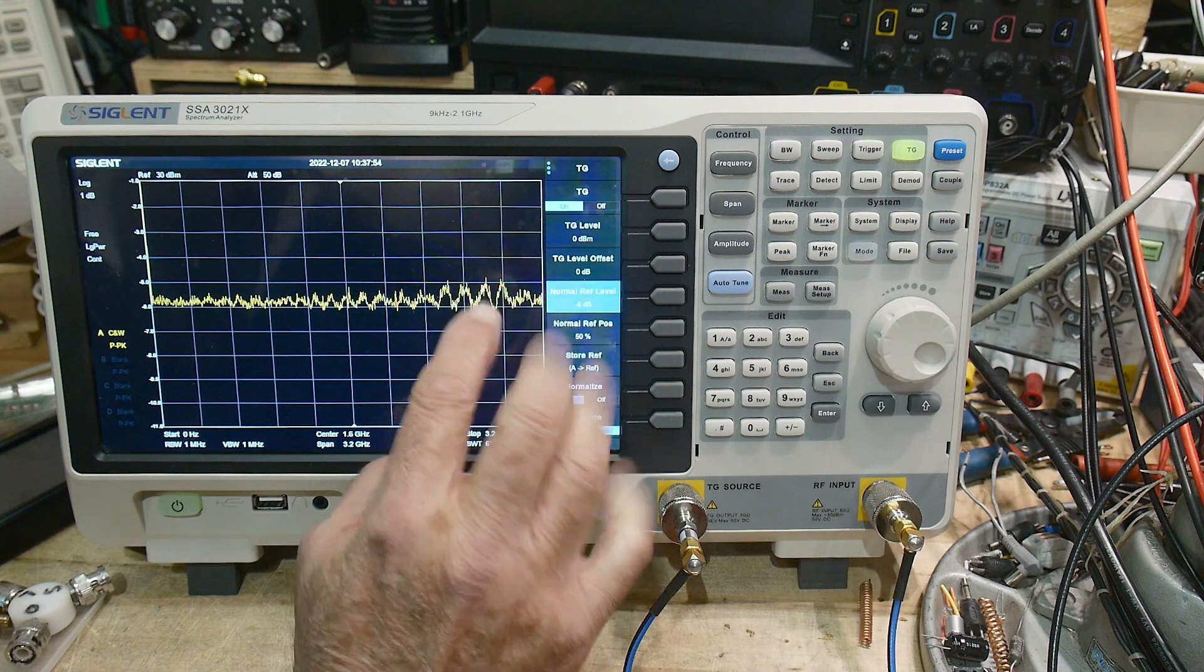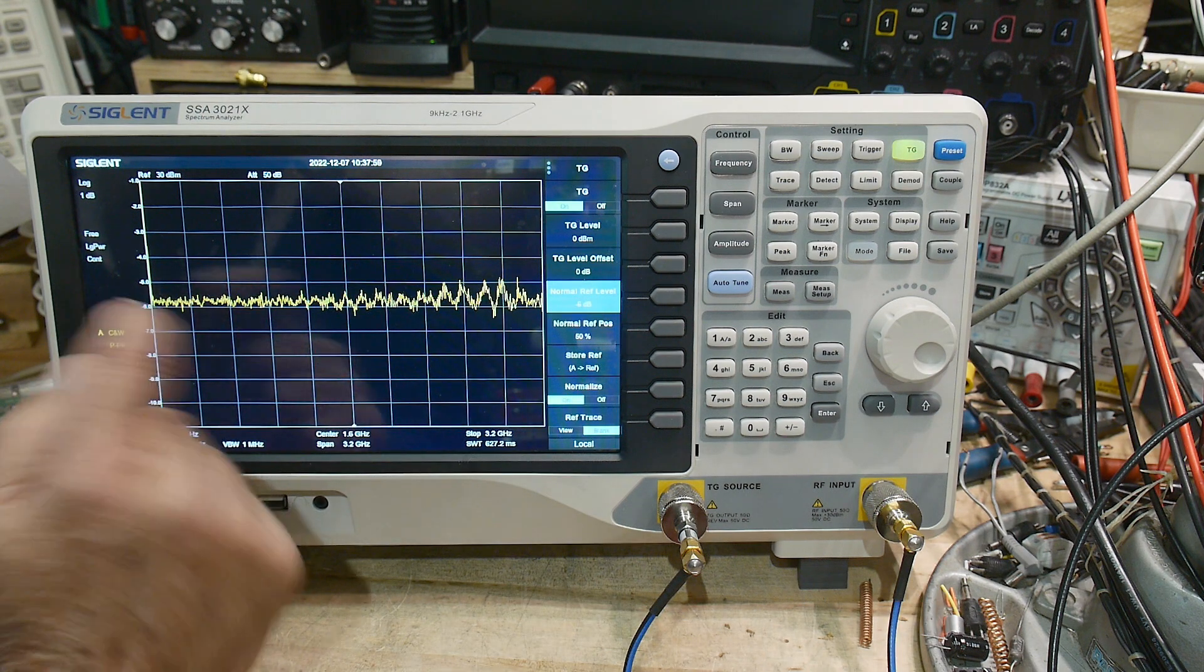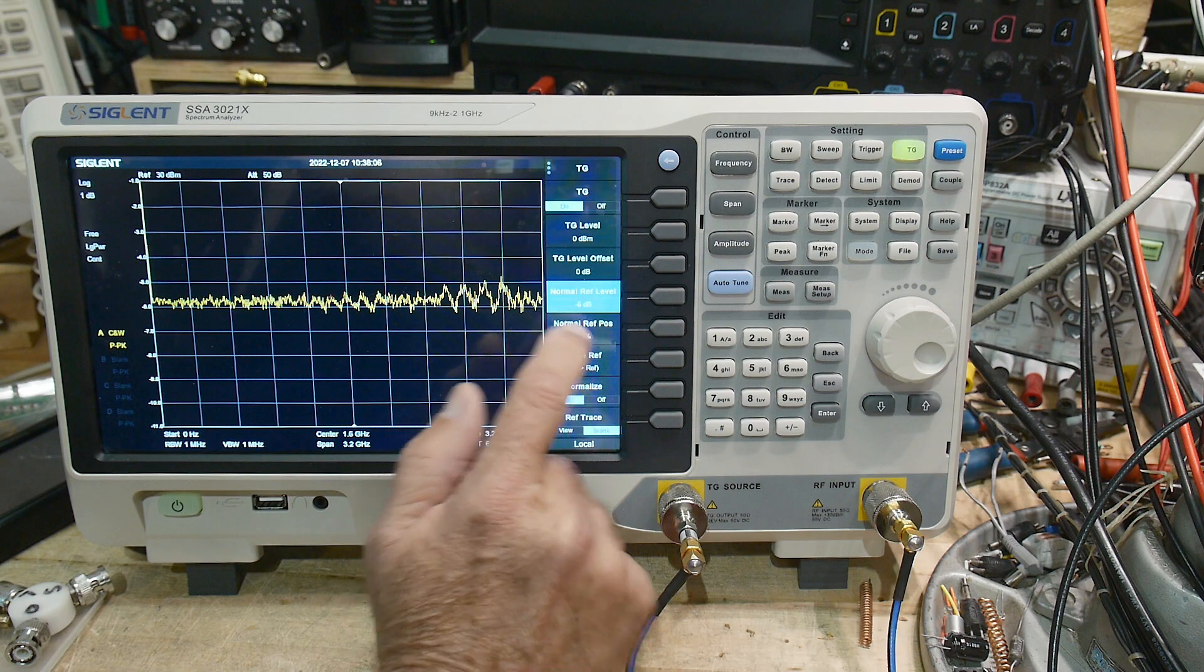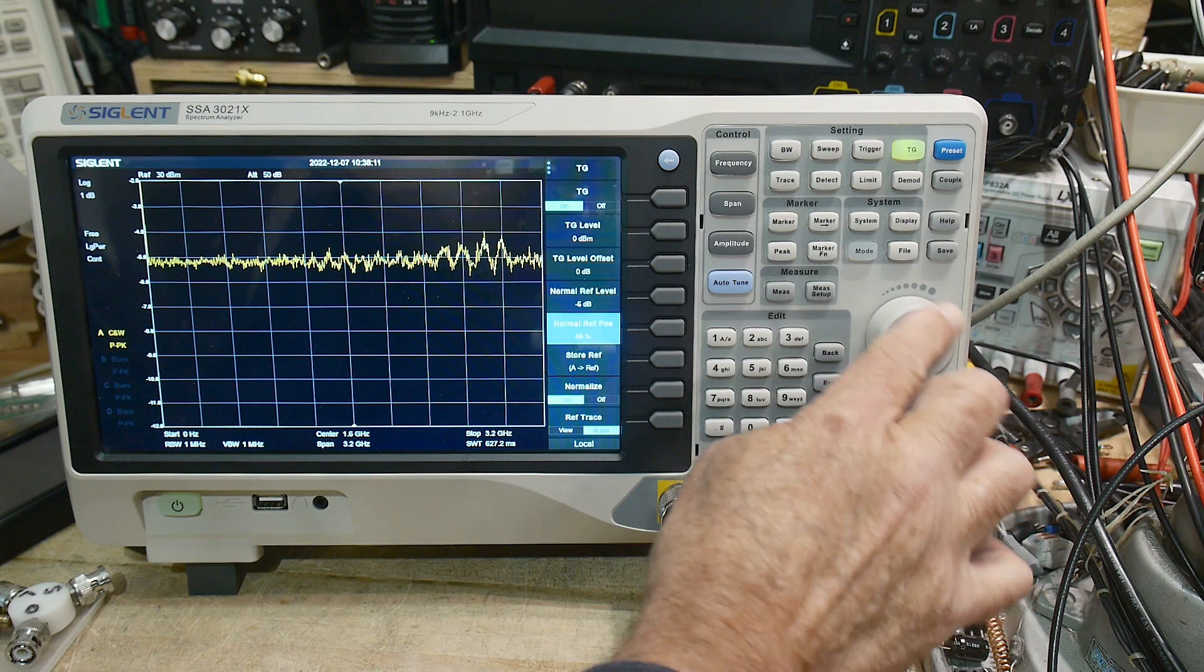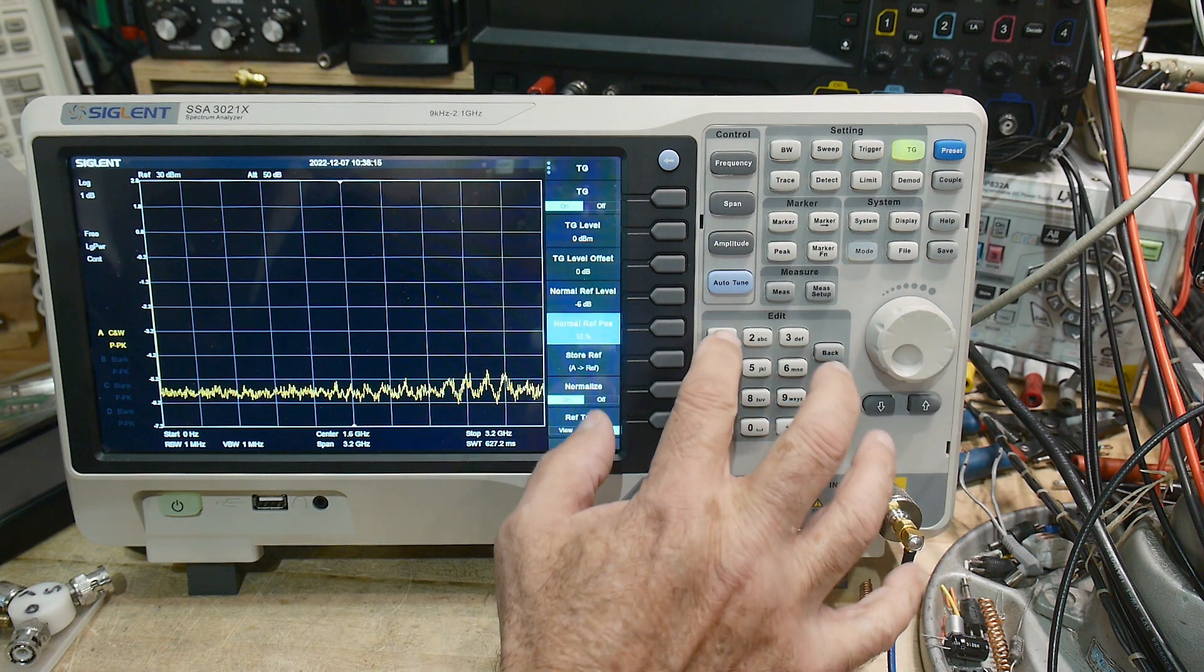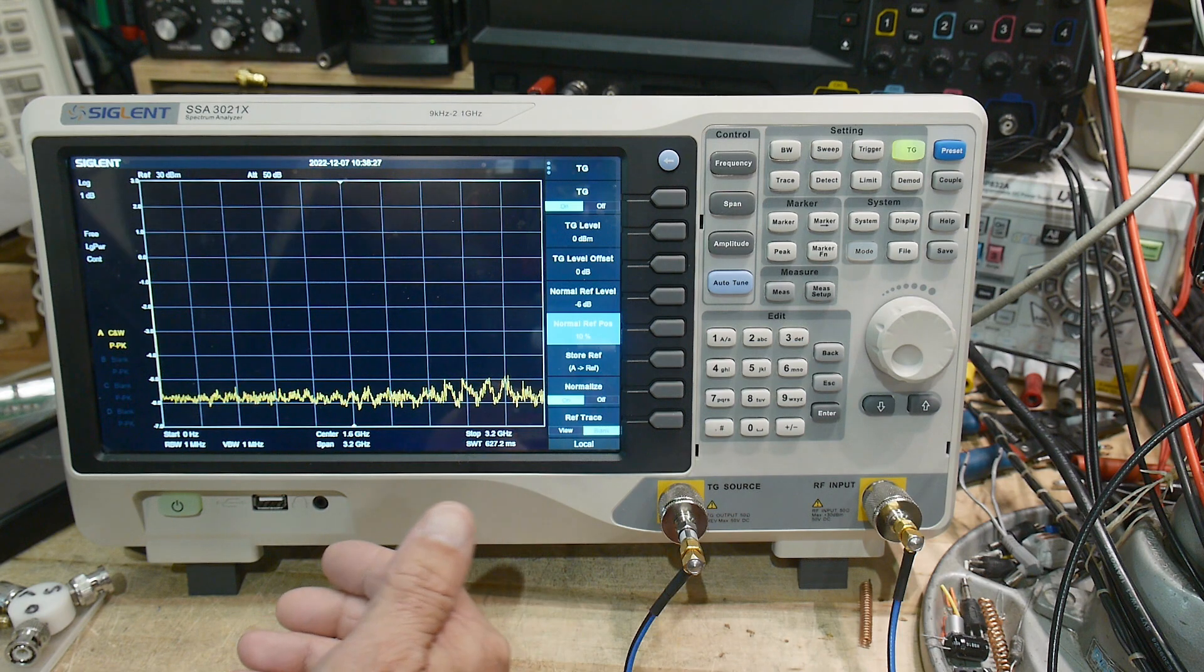It's a bit confusing on this particular one. The reference level is what value do you want this A minus B thing to happen at. We want it to happen at minus 6. Then the reference position is where on the screen do we want it. This just moves it up and down. This percentage means if we set it to 10, it's 10% of the way up. If we want that up at the top, we would say 100%.